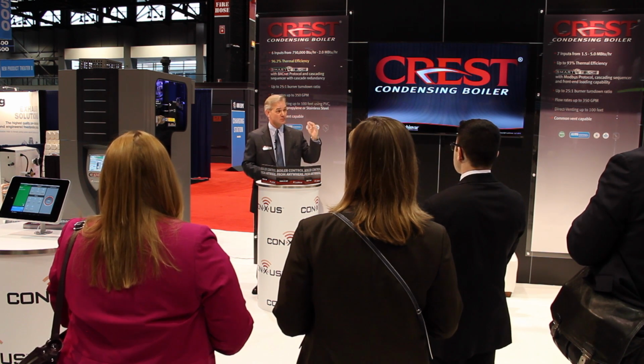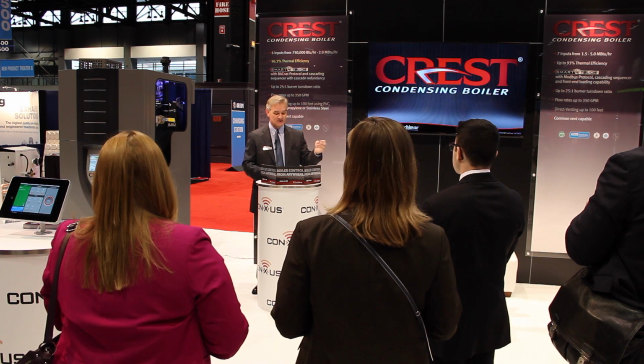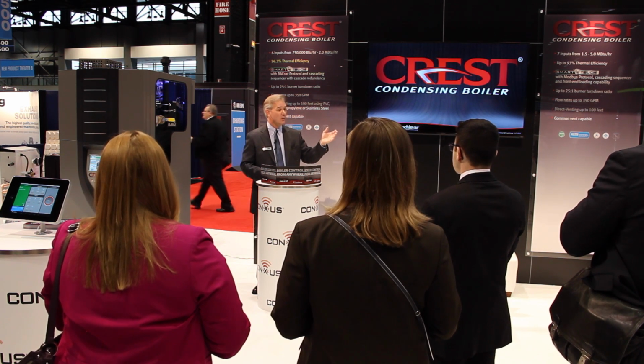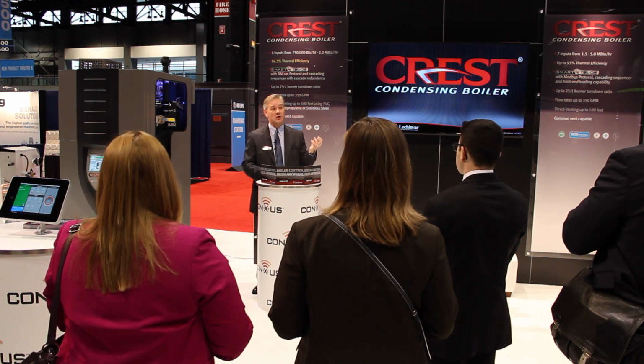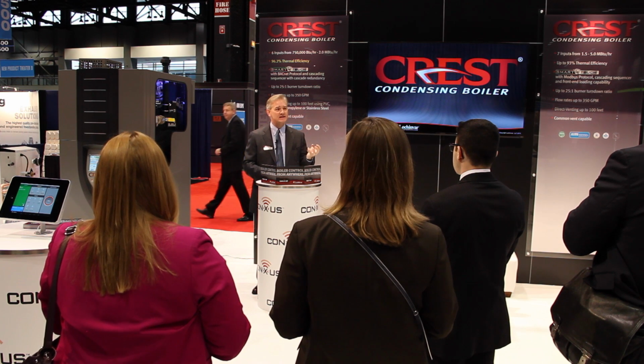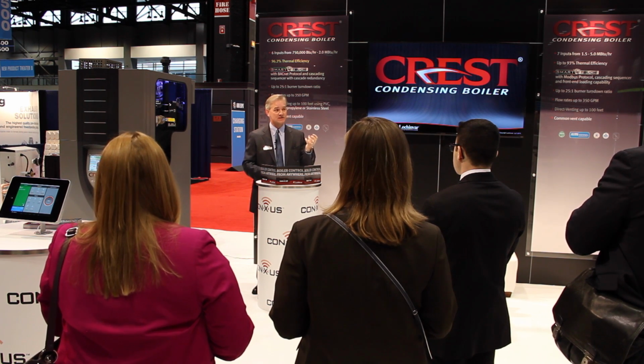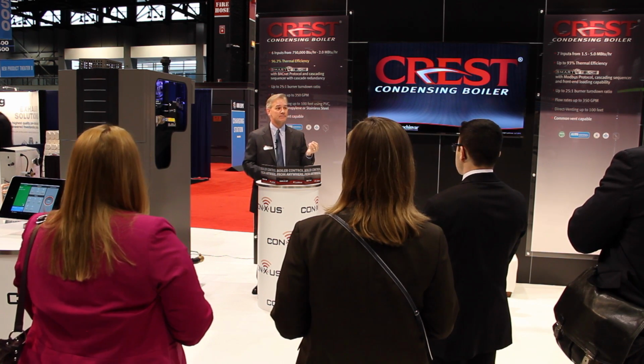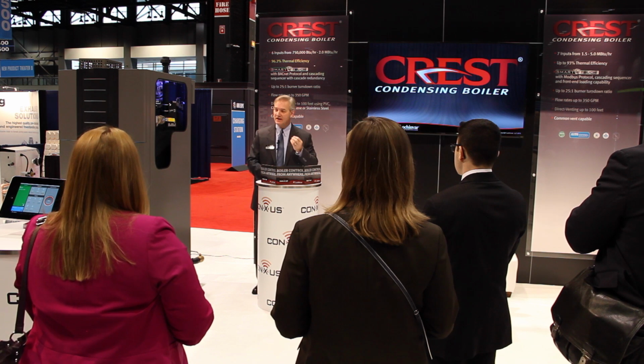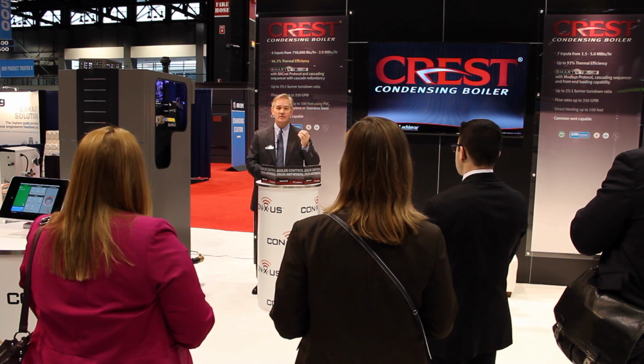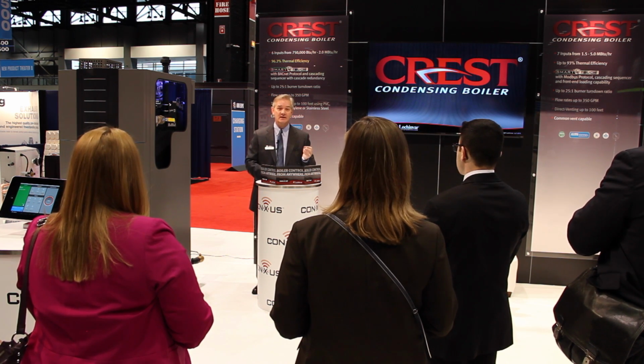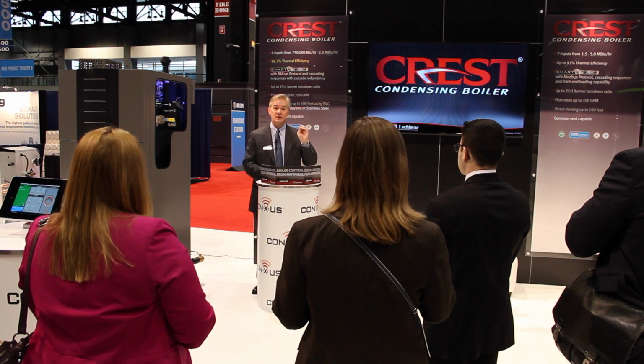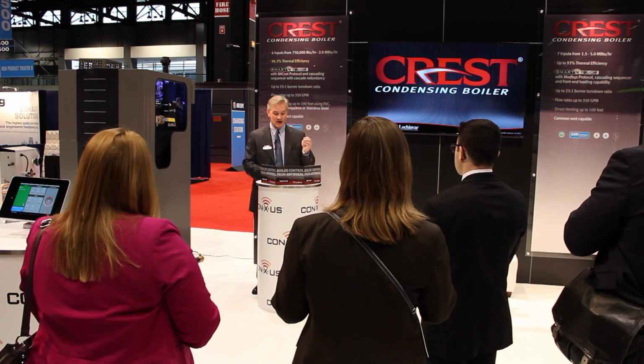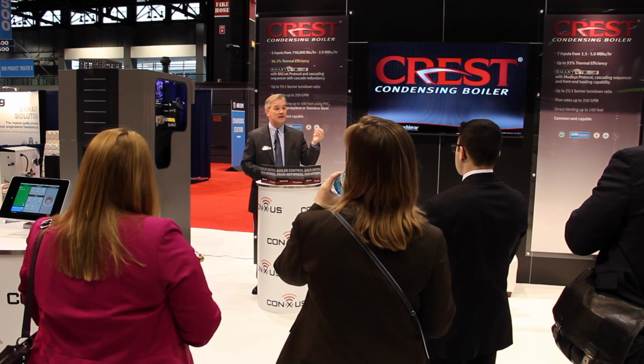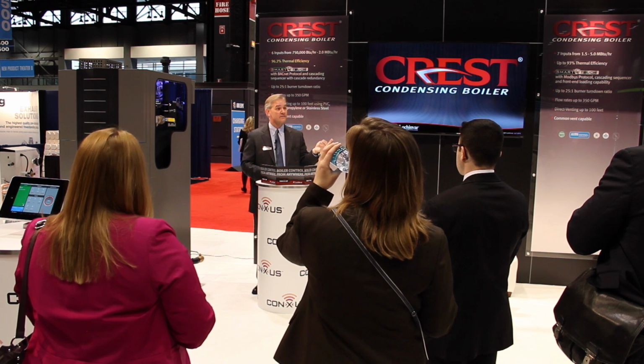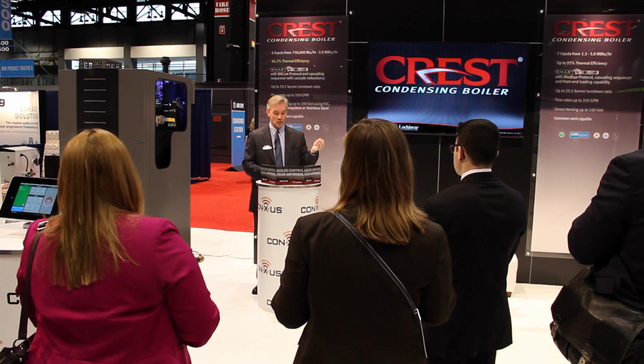96.2% thermal efficiency, which will translate into lower operating costs. We refined and amplified the wave fire tube design, which is the heart of the heat exchanger, to extract more heat out of the heat transfer process and the combustion process, which led directly to the benefit of increased efficiency. We enhanced the Smart Touch operating control with new features such as cascade redundancy, which provides boiler operators complete redundancy in the system. We have new leading burner turndown with turndowns as high as 25 to 1.